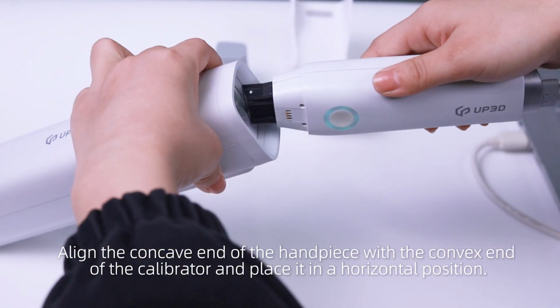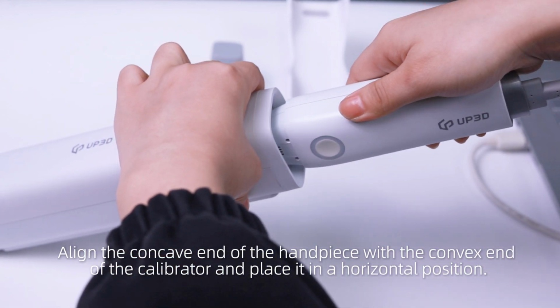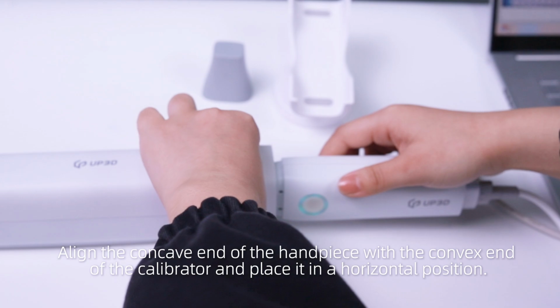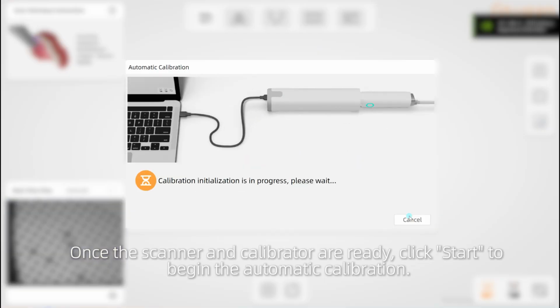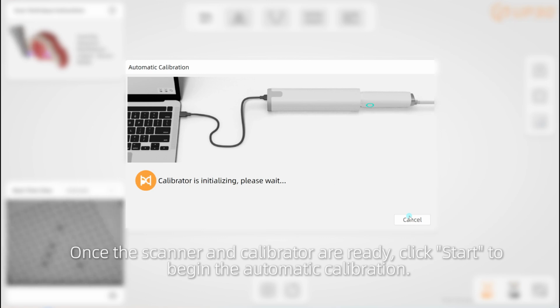Align the concave end of the handpiece with the convex end of the calibrator and place it in a horizontal position. Once the scanner and calibrator are ready, click Start to begin the automatic calibration.